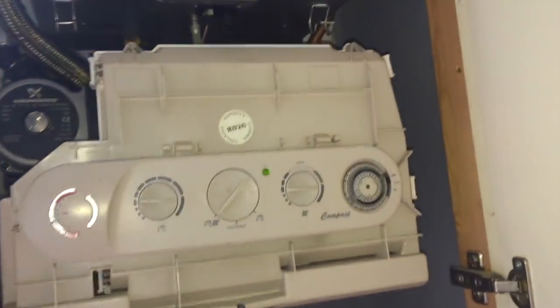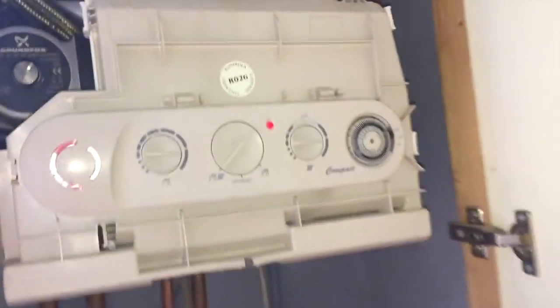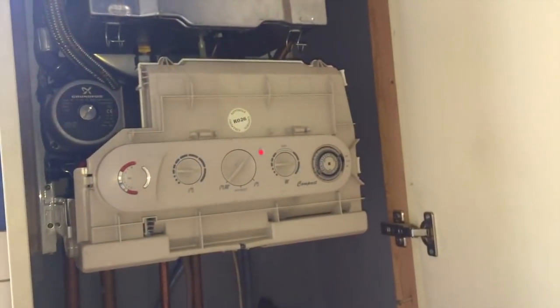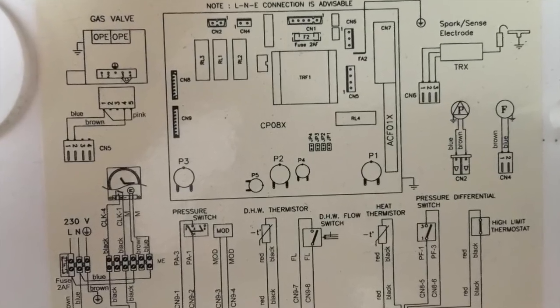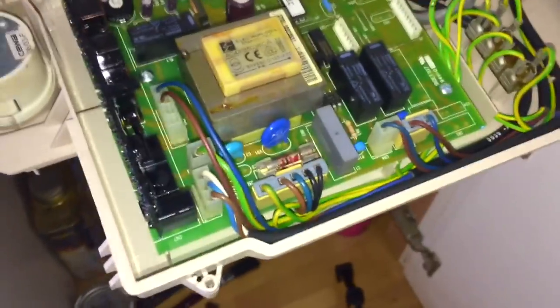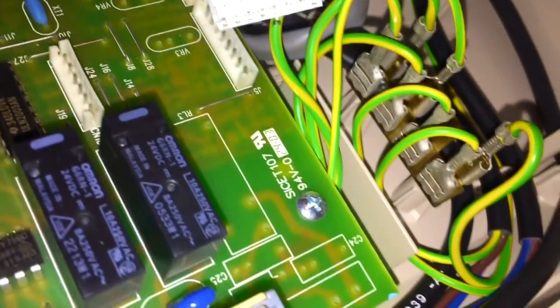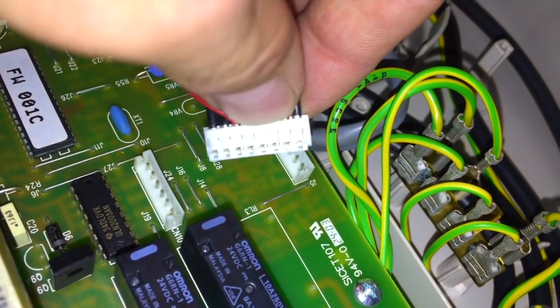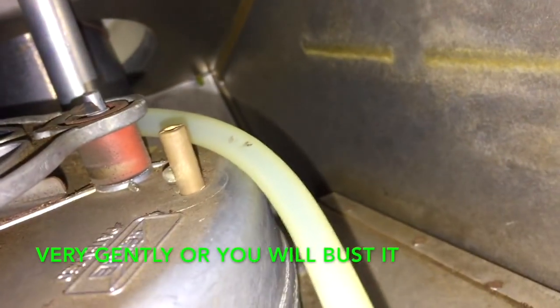So what I'm going to do now, it's going to go red again. Perfect. So the boiler's going consistently to fault, which is really good for testing. Really good. Okay, so using the wiring diagram, I've looked at this, and I think it's these two black wires here. So I'm going to test them. But what I've done, I've got a U-gauge tube on the air pressure switch, so I'm going to make and break that with my mouth like this, and check that them wires, the continuity and whatnot changes.